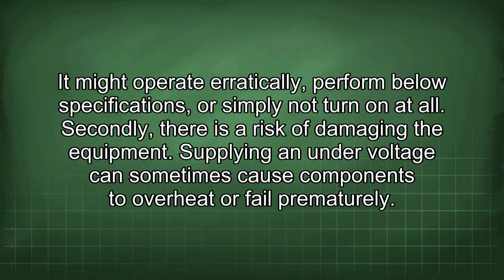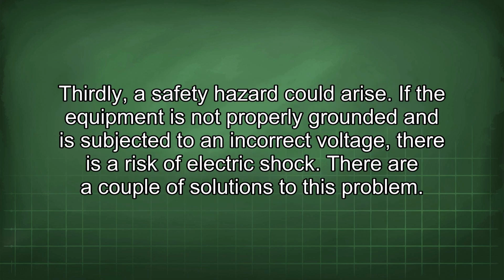Secondly, there is a risk of damaging the equipment. Supplying an undervoltage can sometimes cause components to overheat or fail prematurely. Thirdly, a safety hazard could arise. If the equipment is not properly grounded and is subjected to an incorrect voltage, there is a risk of electric shock. There are a couple of solutions to this problem.